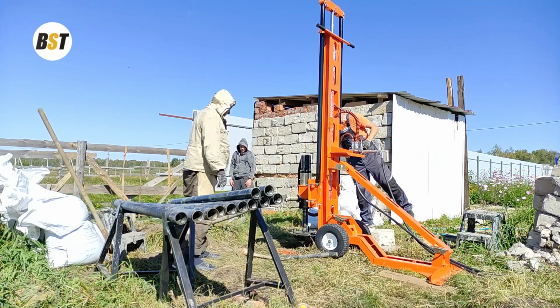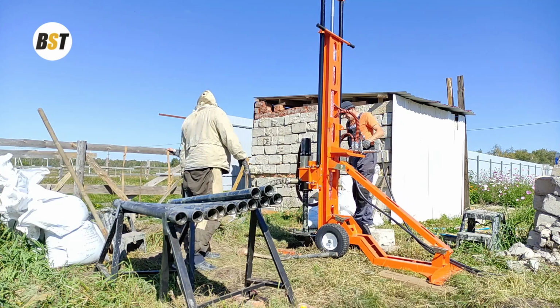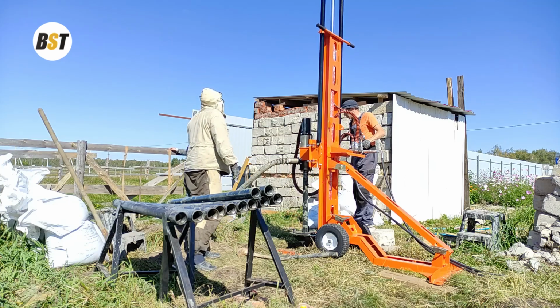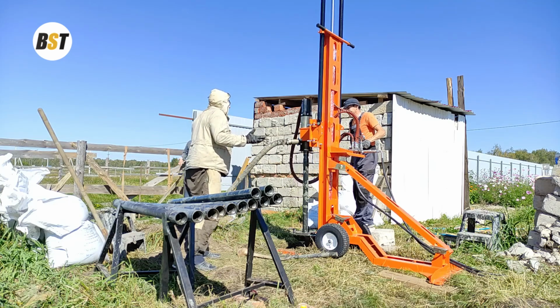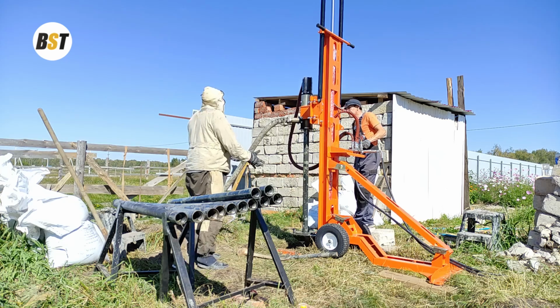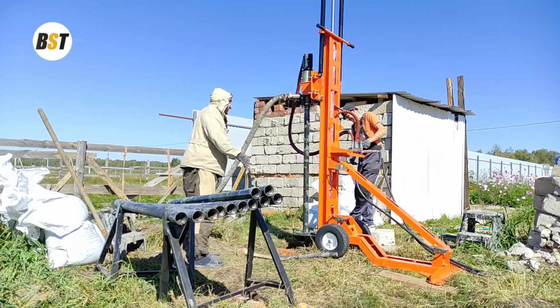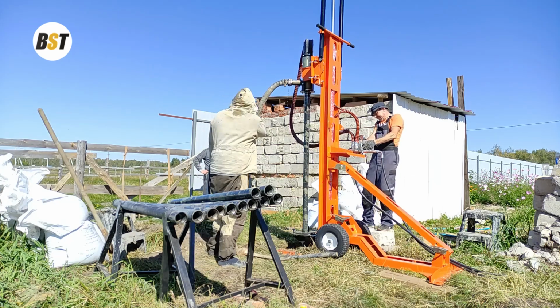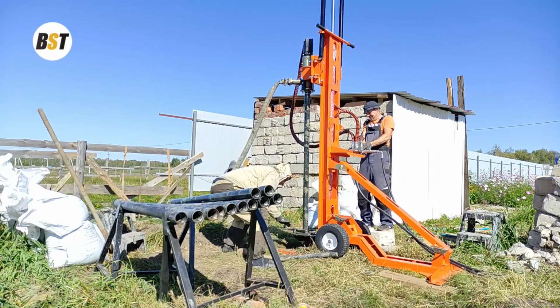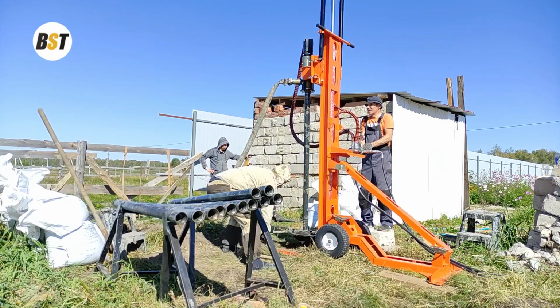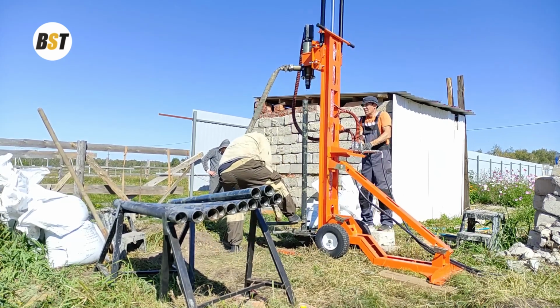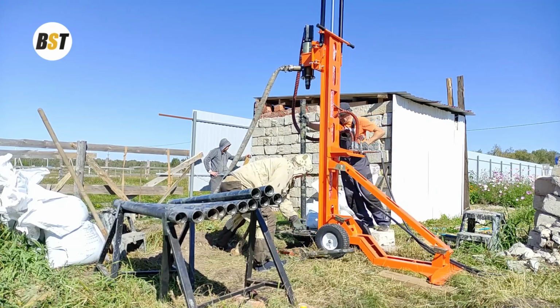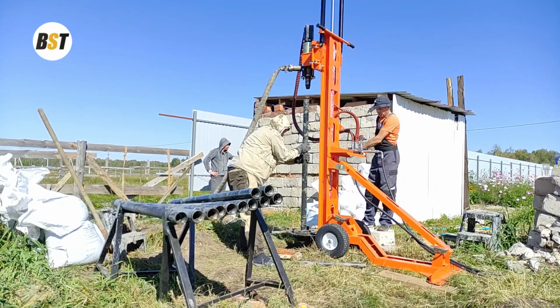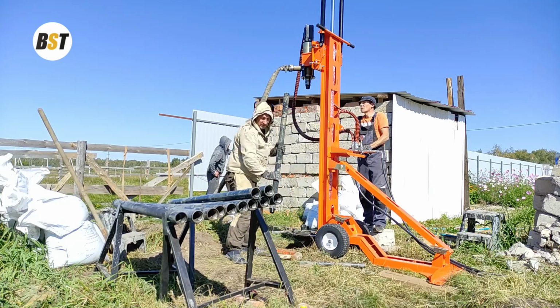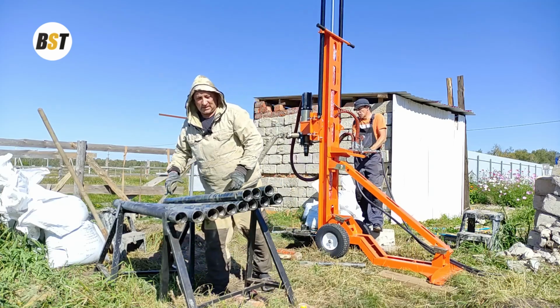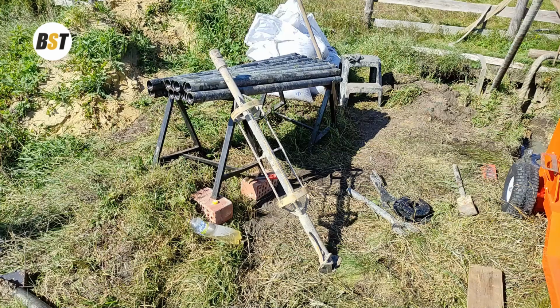Of course, if your resources allow it, you can use more people. A third person can sit at the motor pump to start and shut it down, which is a compulsory procedure: when you remove a pipe, the motor pump should be shut down, otherwise water will splash from the pipe. So to avoid wasting time going to the motor pump each time, you can have a third person purely responsible for the motor pump.